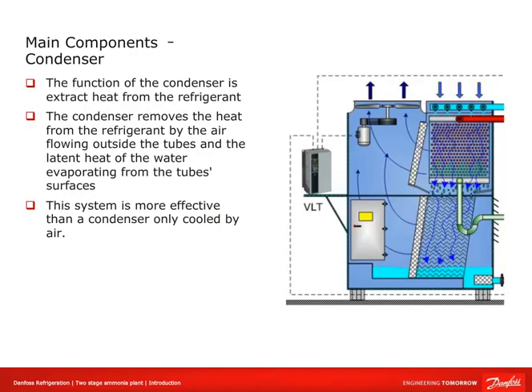The function of the condenser is to extract heat from the refrigerant. In this plant we have an evaporative condenser, which removes heat using air flowing outside the tubes and water pumped to run down across the tubes, so the latent heat of vaporization of the water also contributes to cooling. This is somewhat more efficient than an air-only condenser; however, it requires an environment where the relative humidity of the surroundings is low in order to work effectively.